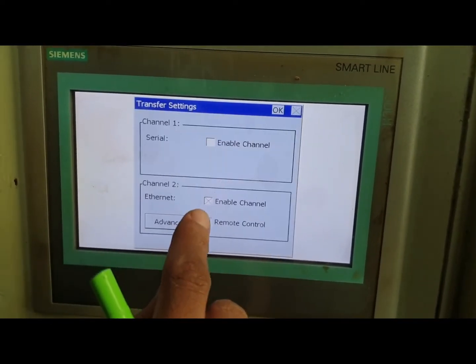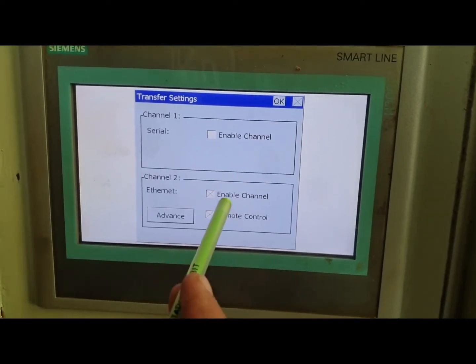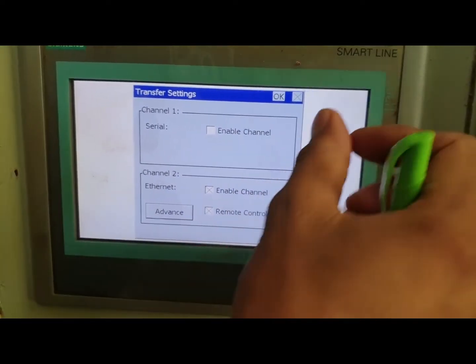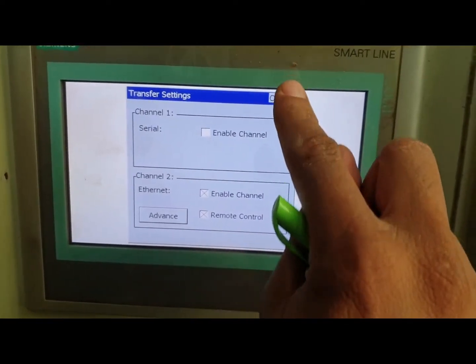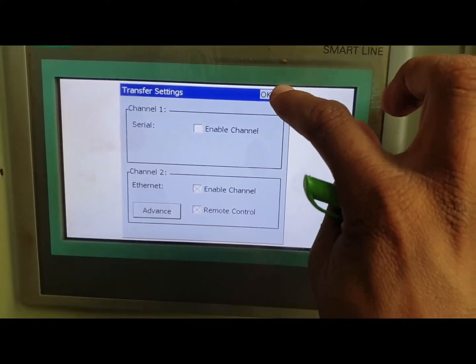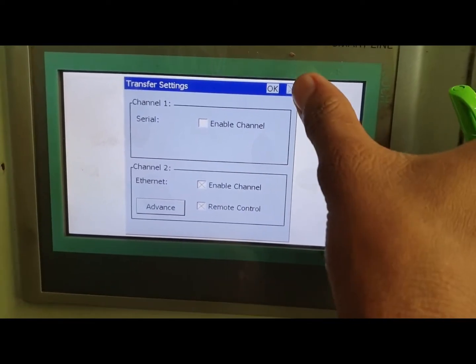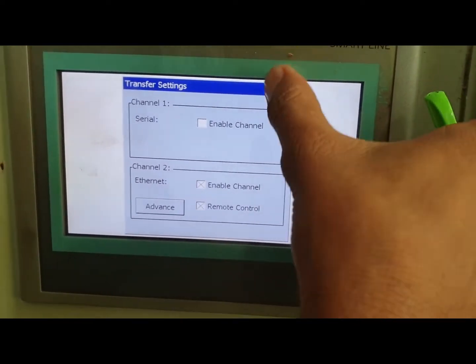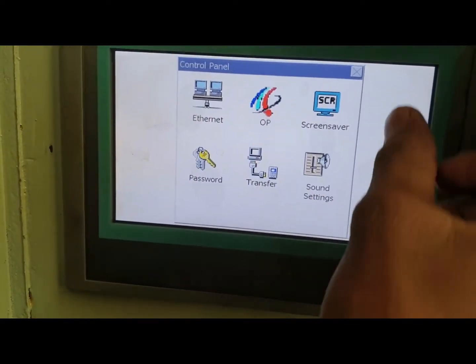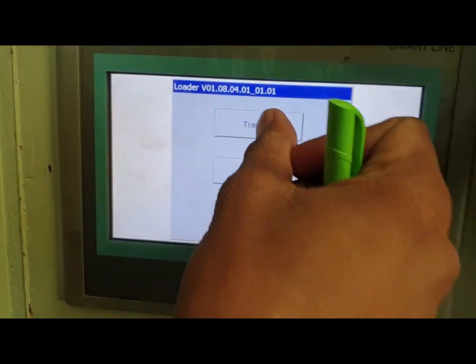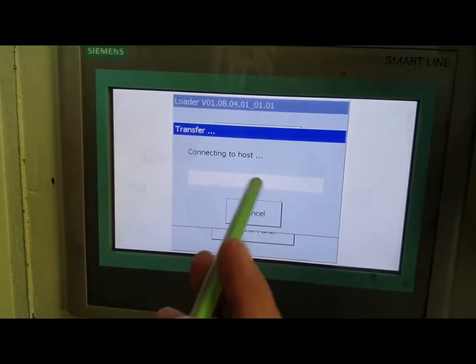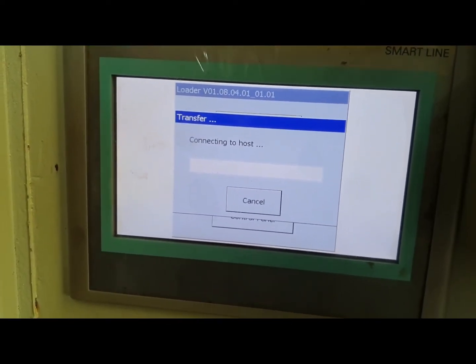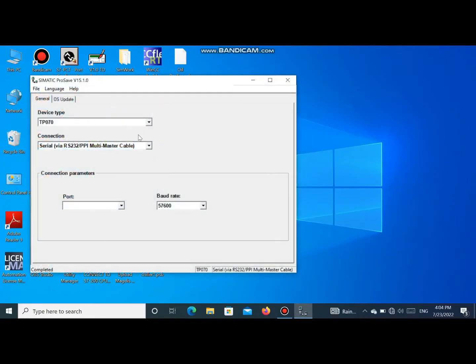Then we go to the transfer mode. Here we have to enable the Ethernet. If it is not enabled, we have to enable this channel. If you don't enable Ethernet channel, you cannot upload the program using Ethernet. Then we go to transfer function. If we don't put it in transfer mode, we cannot connect HMI to laptop.